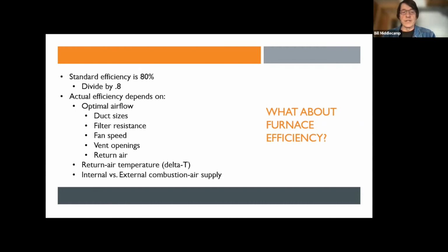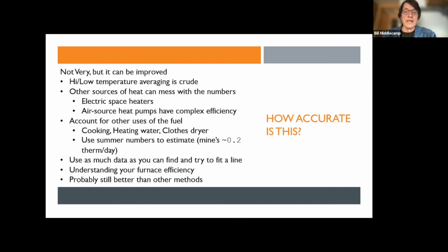Also, the efficiency depends on how much of a temperature difference there is across the heat exchanger. So the incoming air temperature versus the outgoing air temperature. Or imagine incoming air temperature versus the flame temperature on the other side of the heat exchanger. So you can imagine that running your furnace at a cooler temperature actually makes it more efficient. And then whether your furnace takes its combustion air from the inside or from the outside. All these things can factor in. Next slide, please. So how accurate is this?